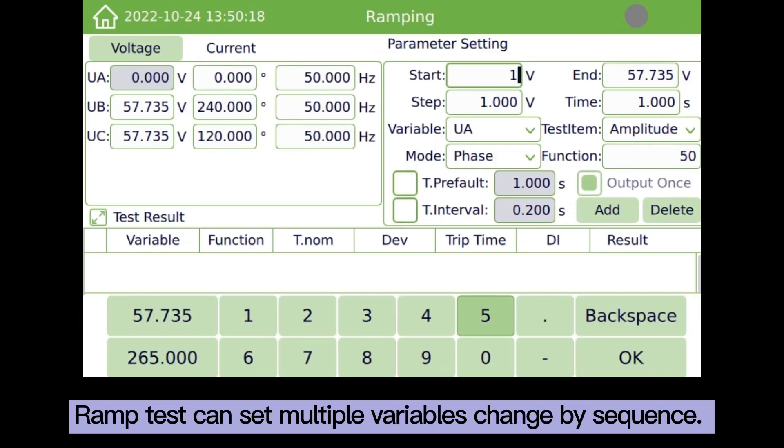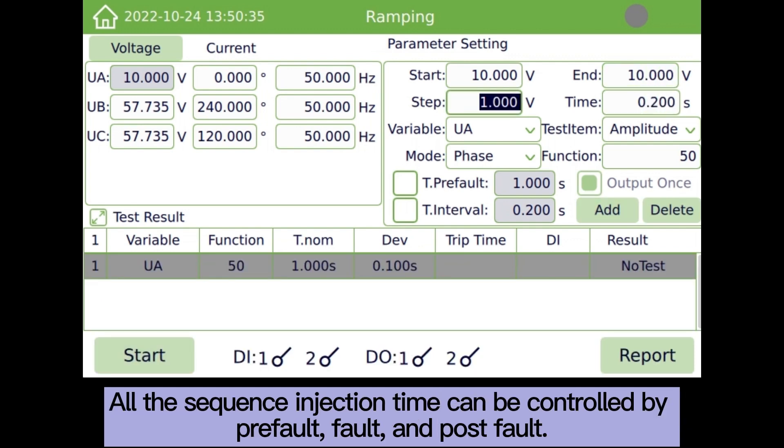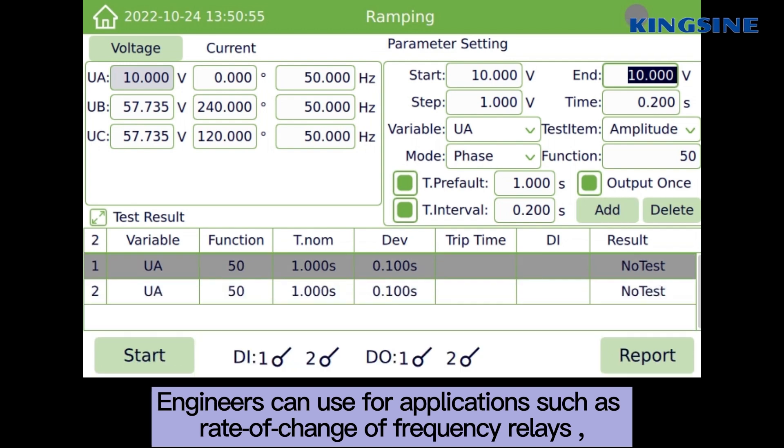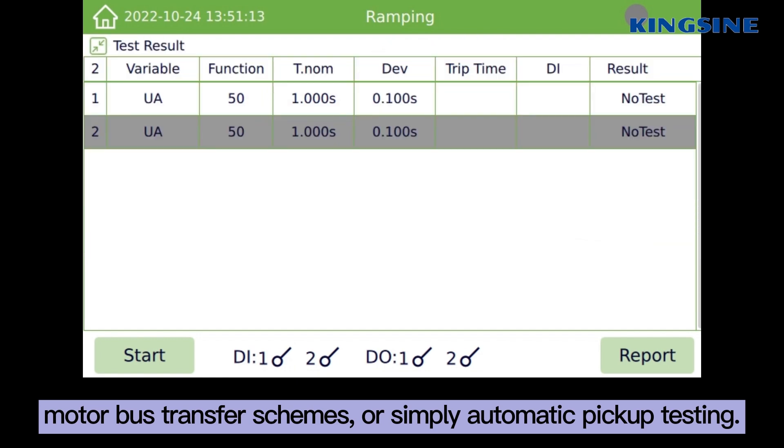Ramp test can set multiple variables change by sequence. All the sequence injection time can be controlled by pre-fault, fault, and post-fault. Engineers can use for applications such as rate of change of frequency relays, motor bus transfer schemes, or simply automatic pick-up testing.